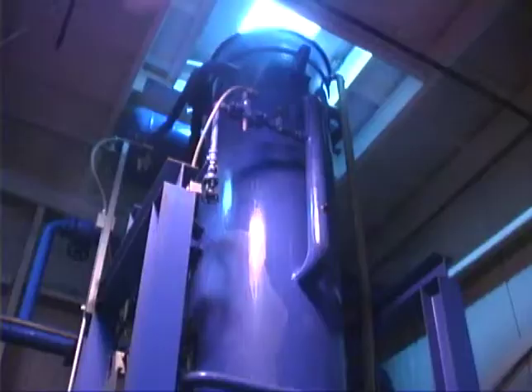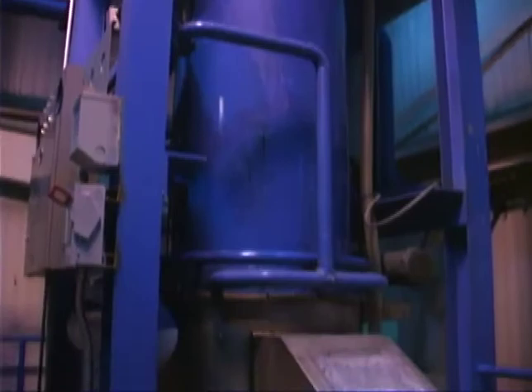Water is pumped up to the top of the machine and is circulated down each of these 400 tubes. Ammonia refrigerant is applied to the outside of these tubes. After the freeze time is done, it runs the anhydrous the other way, which makes it hot, melting down the outside. Ice then comes out onto a drain belt, where the excess water is drained off, and then it goes down to the screw system into the rake bins inside the warehouse.